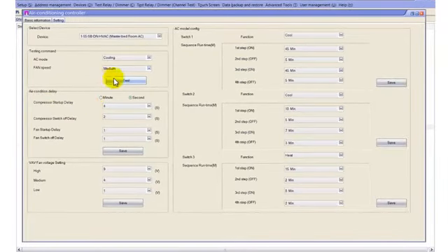speed. You can see here there is an air conditioning delay. Normally we use this delay for the compressor startup and also the compressor switch off delay. What I mean by compressor startup delay and compressor switch off delay, for example, when someone switches on the AC from the DLP, it will take 4 seconds to run up. To take these commands, it takes 4 seconds. Why do we use these 4 seconds? It's a matter of protection, because when someone turns on and turns off, it may damage your compressor at the same time. That's why we keep some delay.